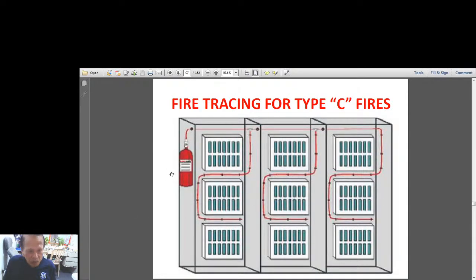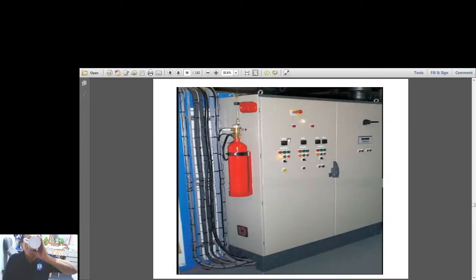And in electrical, usually switchgears, control panels, and electrical switchboards can be provided with the necessary piping to the different components, so that the moment you detect fire, this gas would be spewed in the area and would put off the fire very fast. Here is another installation where you have a switchgear, and you would have the agent in here with the piping. So that means the piping goes inside the switchgear, and therefore it would protect your switchgear against burning.